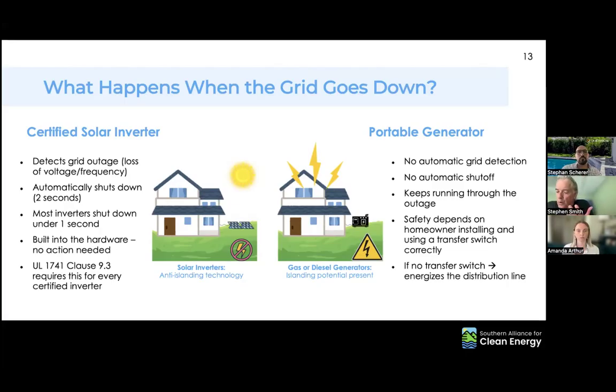If you have a solar system and the sun is out, and for some reason the lines have been disrupted, you may have linemen out there working on the lines, and you could island the generation at your house. There's the potential, depending on the size of the system, for that to backfeed and go back toward the line drop and the distribution transformer, and that could be a problem.